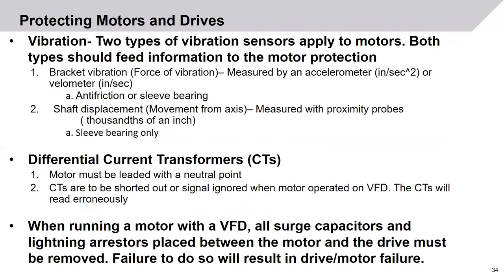There is also current protection via differential current transformers. Motors must be leaded with the neutral point for CTs to work. If a motor is on a VFD, the CTs are either to be shorted out or the motor protection must ignore the signal from the CT when the motor is operated on a VFD, because the CTs will read erroneously. When running a motor on a VFD, any surge capacitors and lightning arresters placed between the motor and the drive must be removed. If they are not taken out of circuit, it will cause catastrophic motor or drive failure.